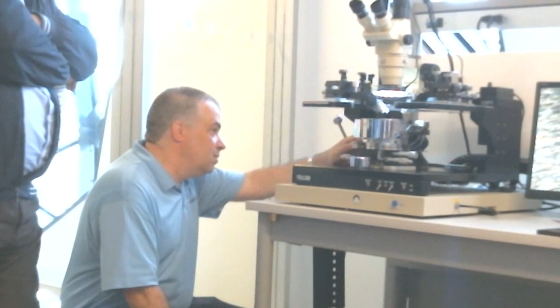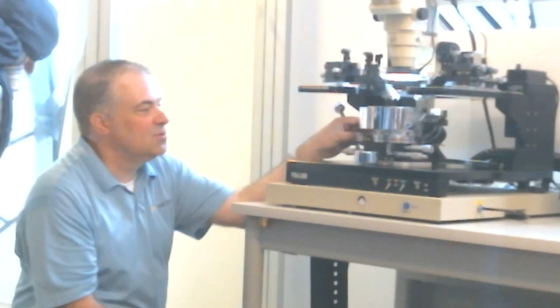If I expose the 2 on the switch, you can use a 2-inch wafer, and there's a ring just under 2 inches around the center that activates on 2. If I go to 4, likewise, if you're using a 4-inch wafer, the vacuum rings open up to just under 4 inches. Lastly, 6, all the way in the back, activates all the vacuum holes on the chuck.